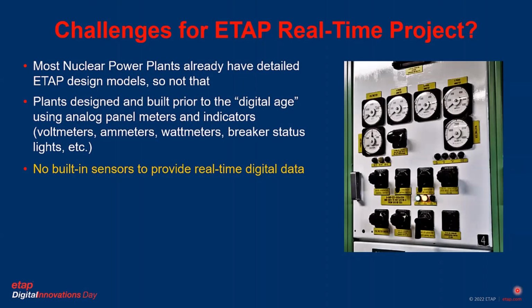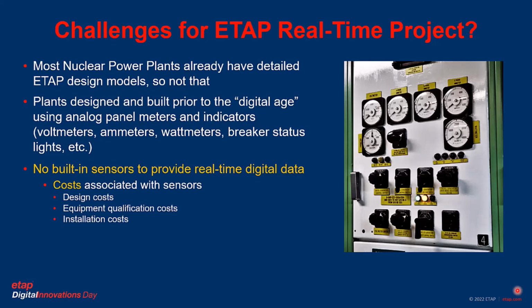So if this is so great, why have we not done it already? What are the challenges for putting in an ETAP real-time system in a nuclear power plant? Well, most nuclear power plants already have a detailed ETAP design model, so it's not that. The real issue is that our plants were designed and built prior to the digital age and use mostly analog panel meters and indicators, things like voltmeters, amp meters, watt meters, breaker status lights, and so on. So we don't really have any built-in sensors to provide the real-time digital data that would feed an ETAP real-time system. And there are costs associated with getting this real-time data.